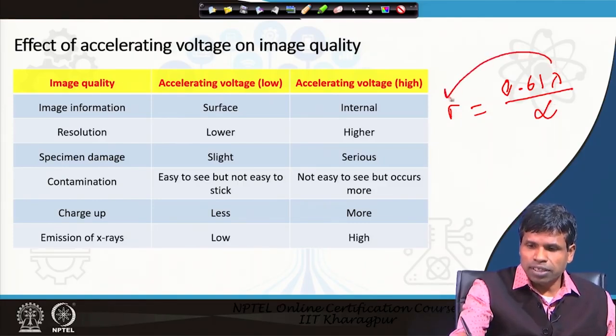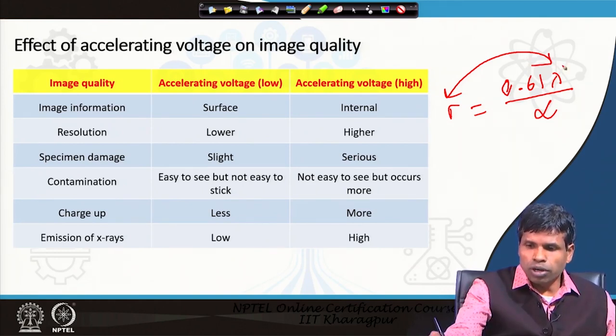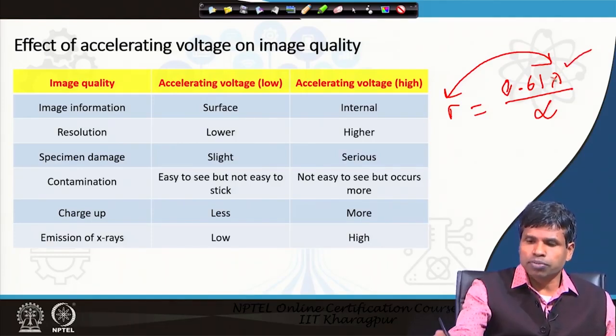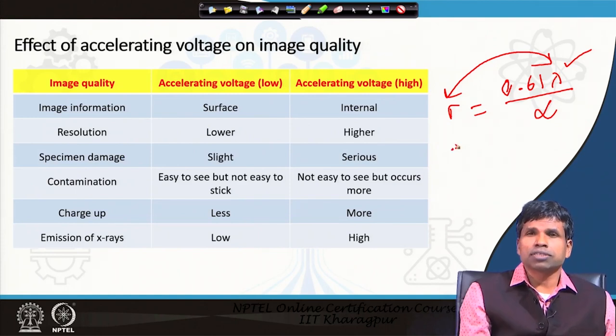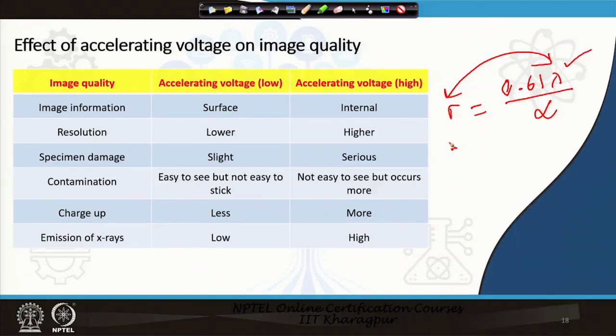The resolution formula is R = 0.61λ/α (simplest form). Here, λ is the wavelength, which is directly proportional to resolution. At lower acceleration voltage, λ will be larger. On the other hand, at higher acceleration voltage, wavelength will be smaller. When wavelength is smaller, resolution R will be smaller — smaller R means the distance between two resolvable objects is smaller, which means best resolution. Resolution is defined as when two objects can be distinguished without losing sharpness — smaller the distinguishable distance, better the resolution.